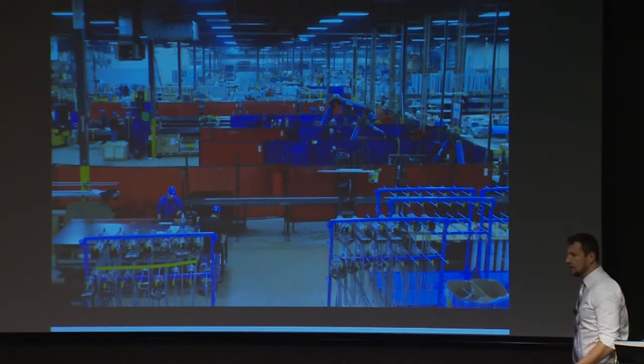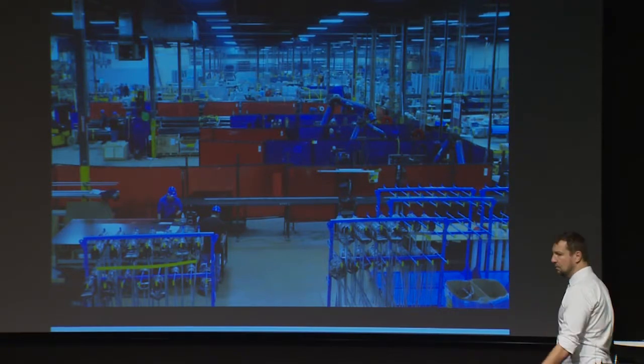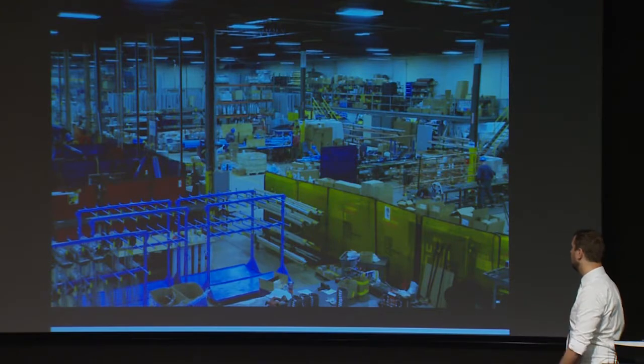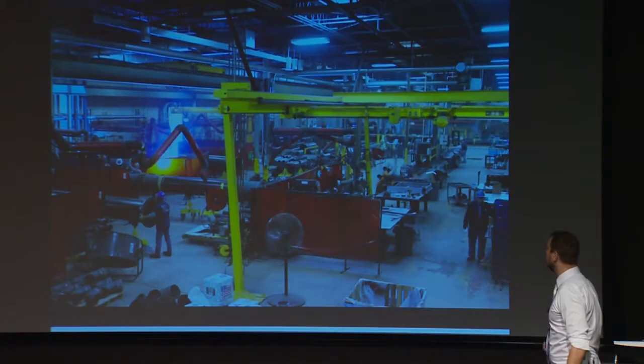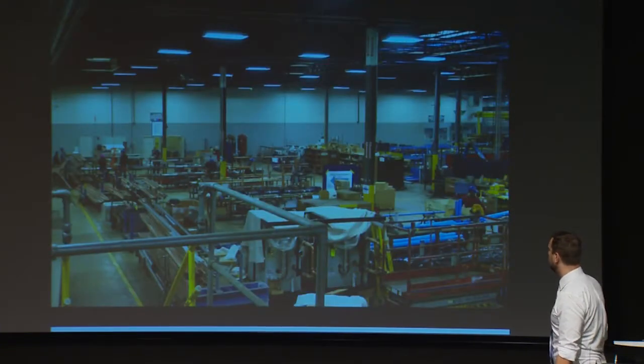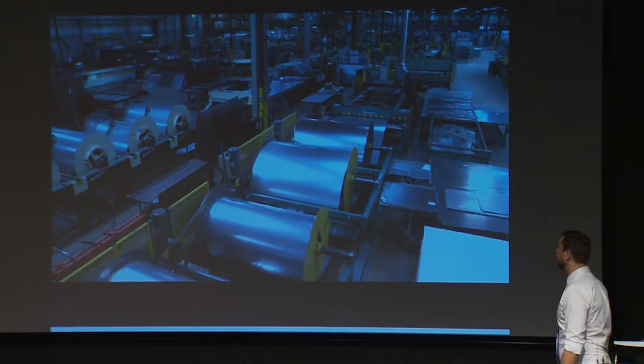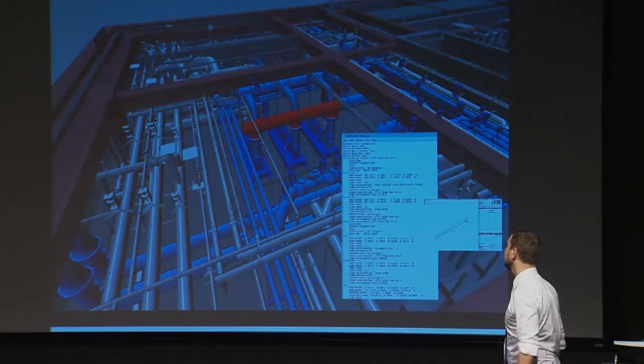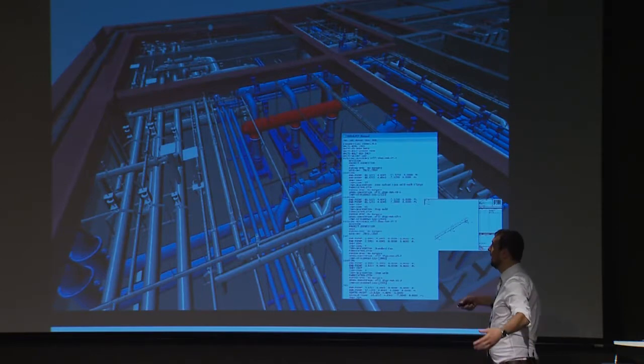This is our 104,000-square-foot space — this is where we're doing our hangers. We've got 15 bays, pipe positioners, and multi-trade space. We have a plumbing prefabrication shop and the pipe shop. We do a ton of copper fabrication. We have decoilers on our main coil line, two plasma tables, and a water jet cutting liner. When you have a piping model defined and coordinated, we go in and tell it where the field connections are. As you build the model it's assuming all shop welds; then once we've collaborated with our foreman and understand crane time and logistics, we go back and designate all field connections.